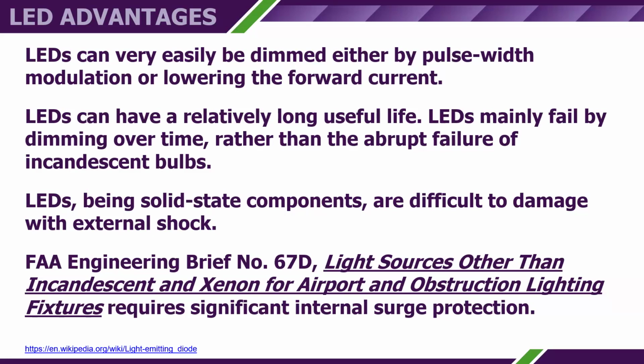And Engineering Brief number 67 says light sources other than incandescent and xenon for airport and obstruction lighting fixtures require significant internal surge protection. So the FAA criteria for manufacturing of LED fixtures requires a pretty good system of surge protection internal to the fixture. I will tell you that new fixture installations should include equal potential counterpoise, lightning protection system, and field lightning arresters. Field lightning arresters are very similar to the arresters that the FAA mandates on the output of a constant current regulator, except they're designed to be installed in the light bases.